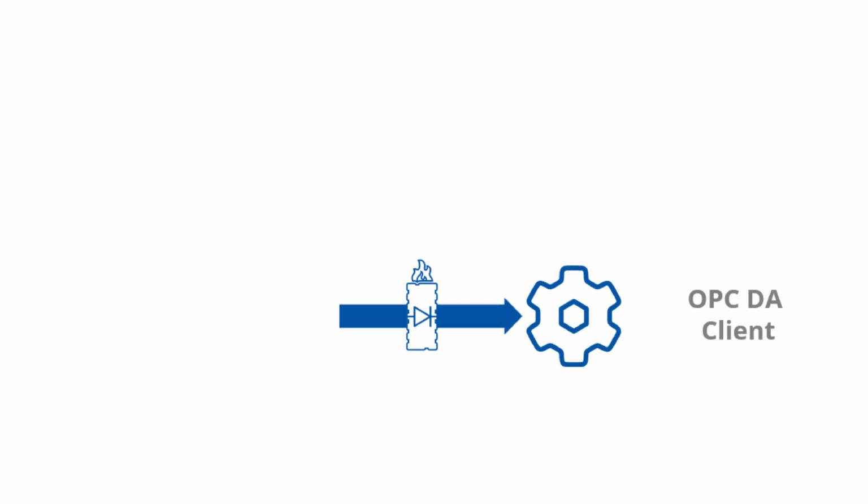When the connection is lost, you want to mark the data quality for all points over there on the master as Not Connected. So choose that option. Check the Run in Data Diode Mode option to enable data diode support. If you don't have a hardware data diode, this mode enables software emulation. Click OK and Apply. Now switch back to the OPC client computer.